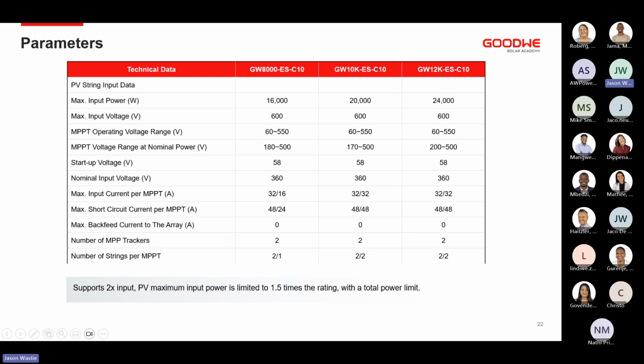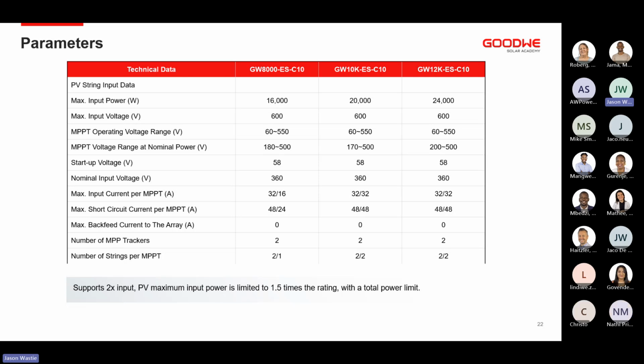PV string input data. On these inverters, we do allow for the max input of double the inverter capacity. That's due to PV oversizing, but I'll show you that now. The MPPT operating voltage is between 60 and 550 volts. So this is quite a unique feature for Goodwe for this inverter, not only this one, but other inverters going forward as well. Essentially what this means is that almost as soon as it starts up, with the startup voltage being 58 volts, once it hits 60 volts, the PV production will start.